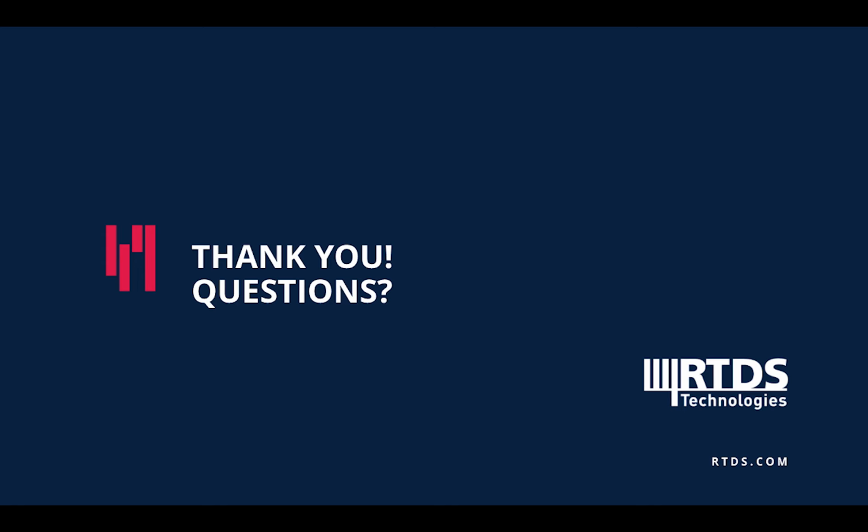I don't know, Christian, did you want to show, for example, the SCD editor? I don't know if we have time for that. Yeah, the process for doing the mapping for GOOSE messaging is a little bit more involved because typically it'll involve the use of multiple softwares. So you do some of the mapping within the SEL tools. For example, you might use the SEL Architect tool to do some of the mapping. And you would also use our SCD editor tool to do the mapping on our side. So it's a combination of different tools in order to do that. It's not as simple as a simple points file.